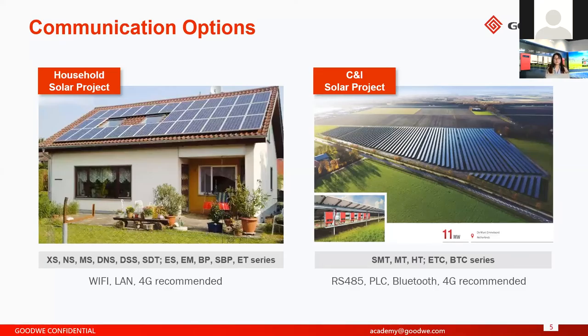But for commercial projects, first, there is a lot of data, and then the project may cover a larger area, and there is a higher requirement on security and the secure communication and transmission of your data. Then wired communication like RS-485 is recommended, but PLC is more economic because it will save you extra communication cables.